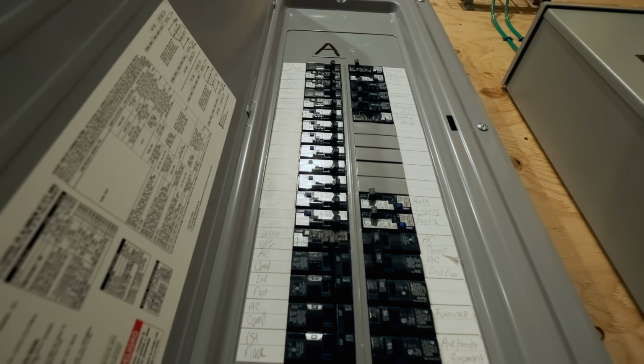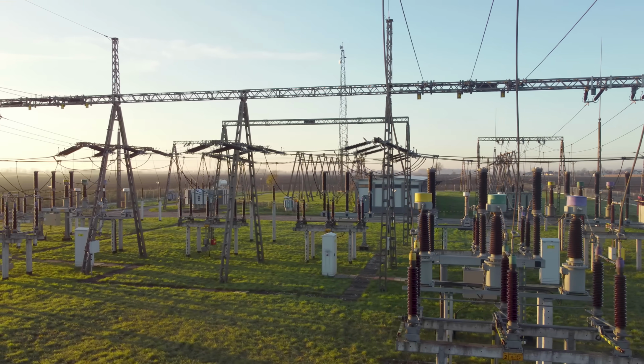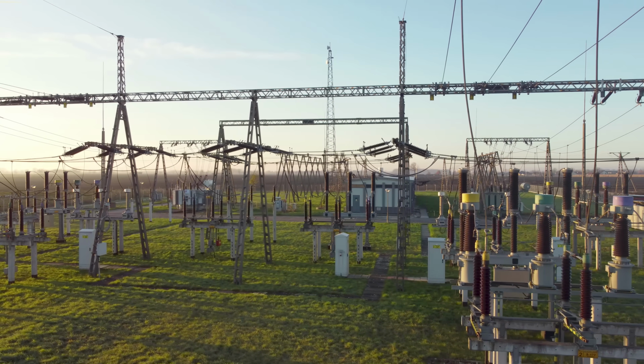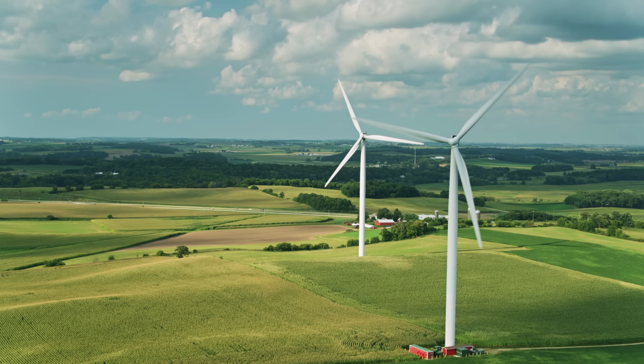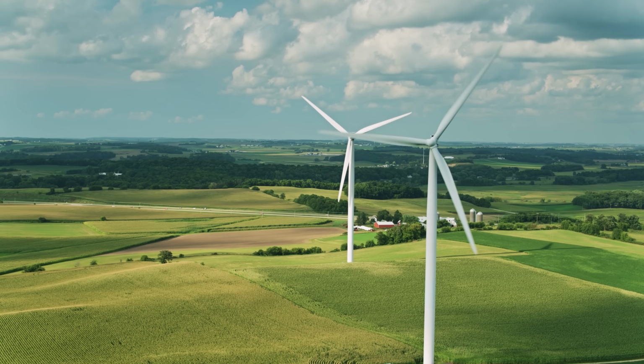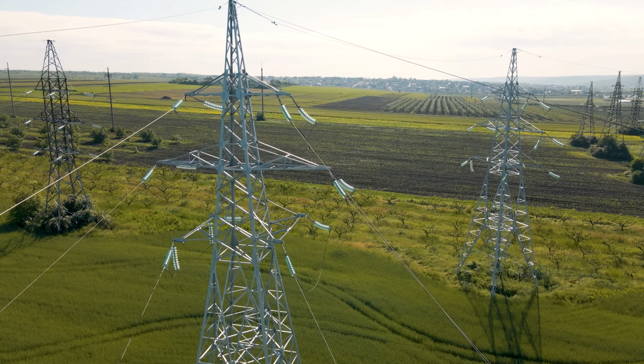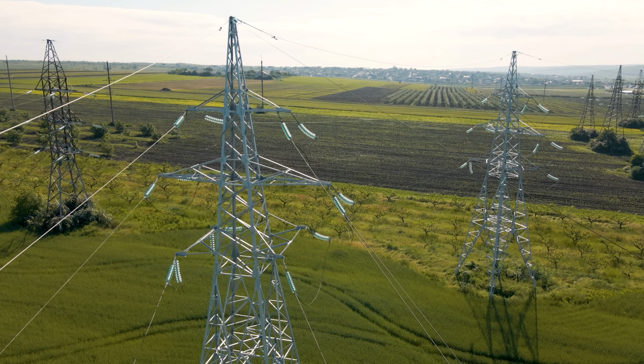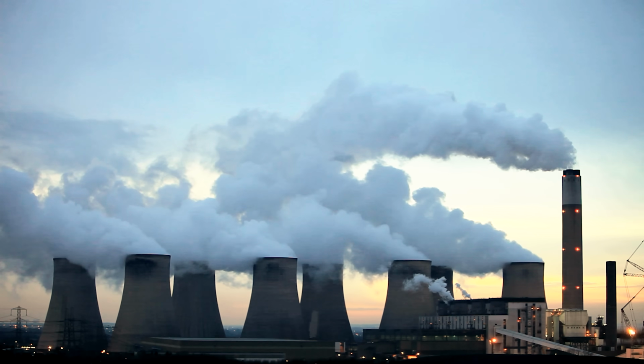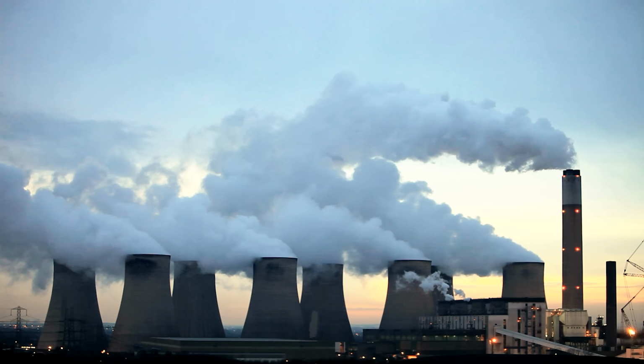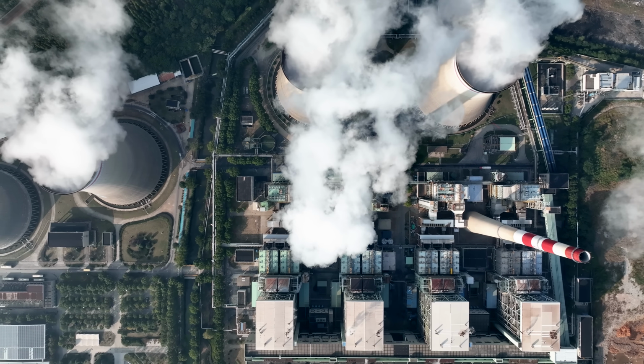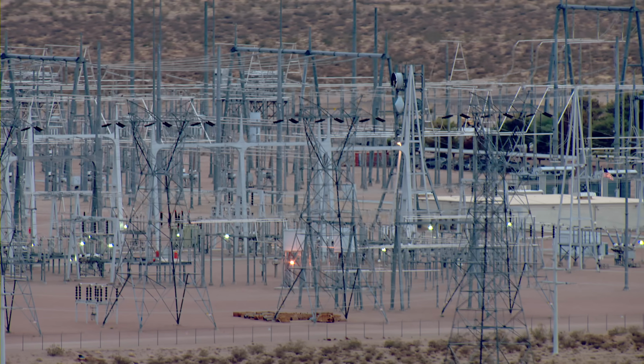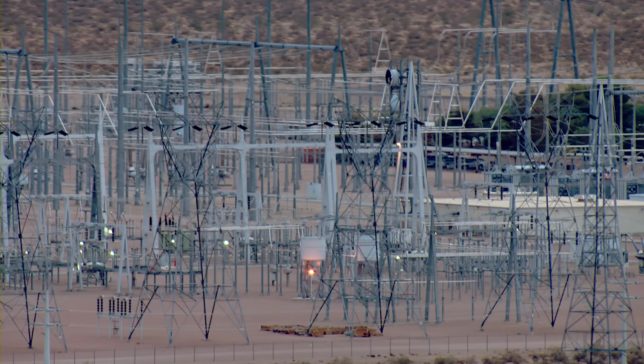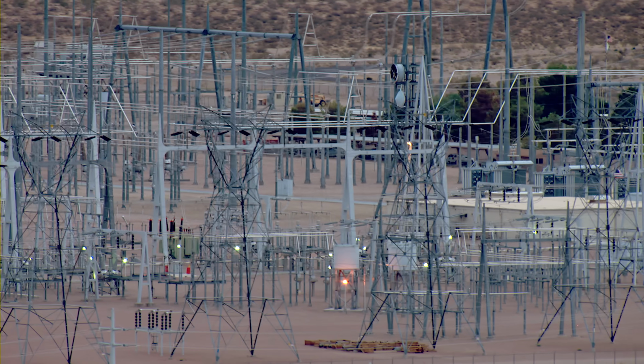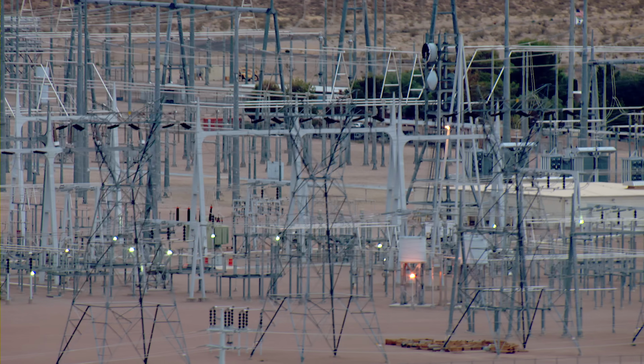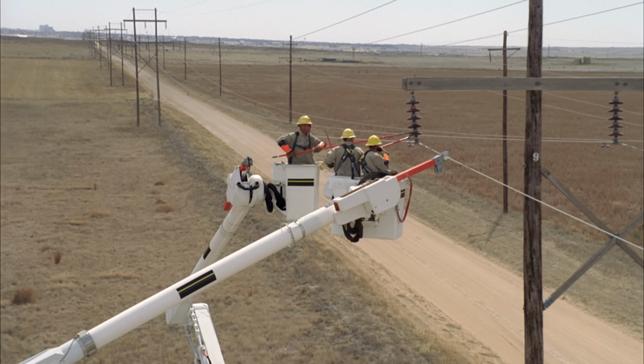But that doesn't mean it doesn't come at a cost. It still has to flow through the power network, where some gets lost as heat from resistance in the lines. So the generators have to make, and the transmission lines have to move, more power—in some cases, a lot more than is actually being used. Reactive power can make up a big part of the total load on the system, even though it's not doing any work. Just having the infrastructure in place to handle it is also costly. The conductors, transformers, and generators on the grid have to be sized for the total current that needs to move through the system, not just the current that does work. And that stuff is expensive.